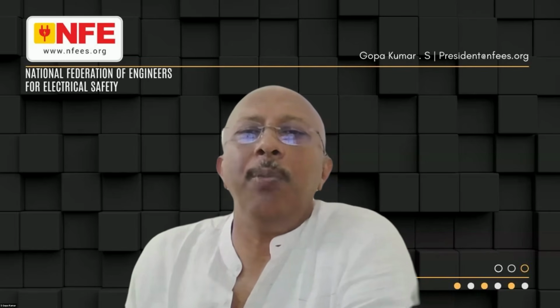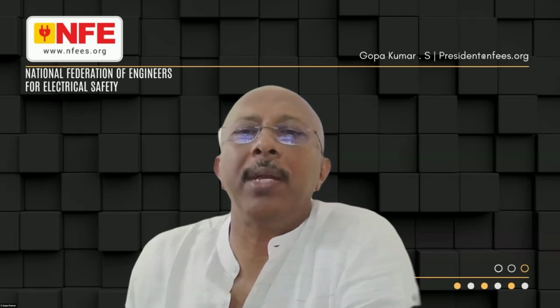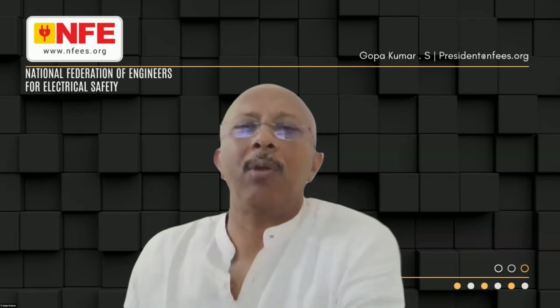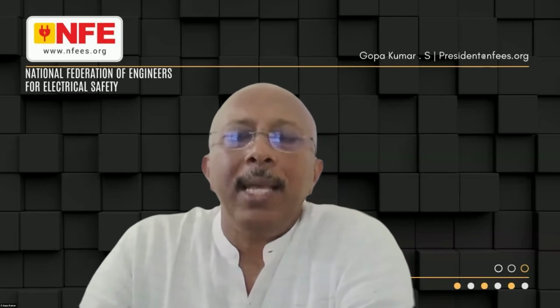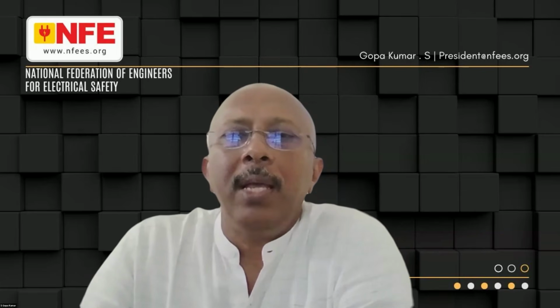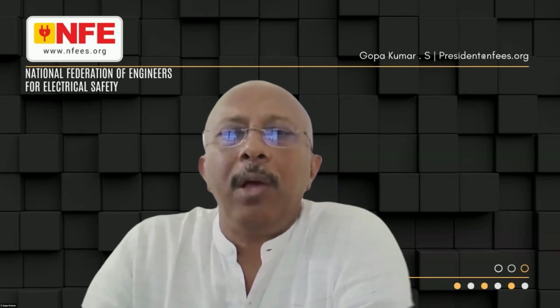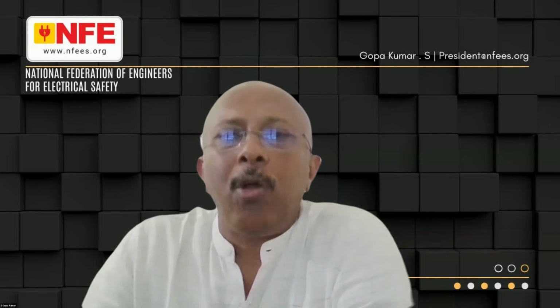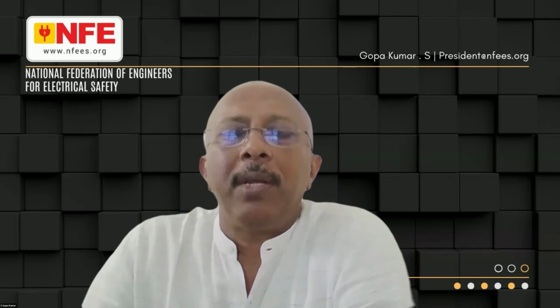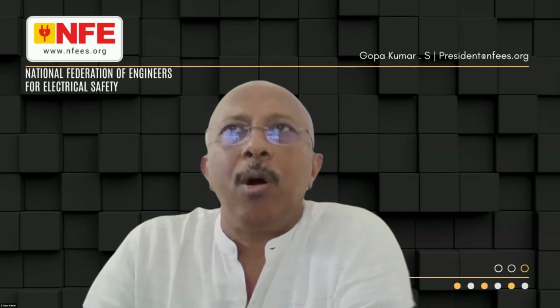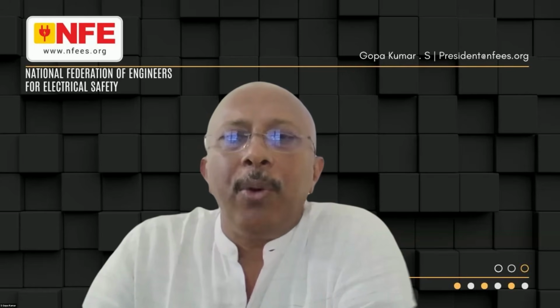Dr. Pandian, how many earthings are required for 1000 kVA, 11 kV by 0.433 kV distribution transformer as per CEA regulation? If you are asking how many earth pits, I would say you need to have only one earth electrode. You have to have a common bus bar, neutral of the transformer, as well as body of the transformer must be connected to the common bus bar. The common bus bar can be connected to an earth electrode, and this earth electrode can be, the best is to have the foundation earth electrode.